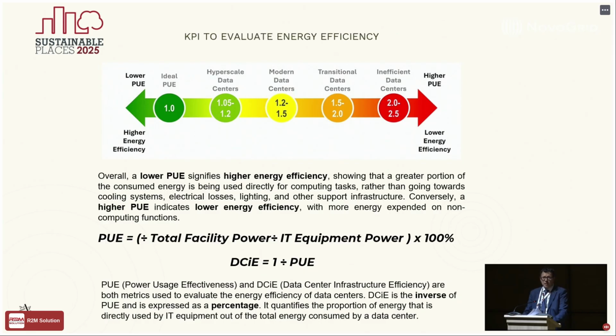One of the most important key points for efficiency is the PUE. It's a very simple indicator that measures the total facility power over the IT equipment power. That means if 100% is the need for IT, a PUE of 1.5 means you need 50% more to ensure the operation of a data center.